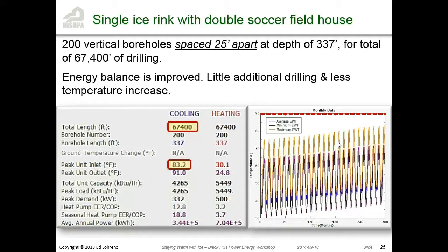Well, okay, if you're not making ice, for example, then the refrigeration load will be a lot smaller because you're not using the ice, you're not flooding it, and you don't have the radiant load on it as much or anything like that, so the refrigeration system isn't going to run as much. And then what you may have to do, if you've got a bigger heating load than you are getting from the ice, is extract heat back out of the ground.